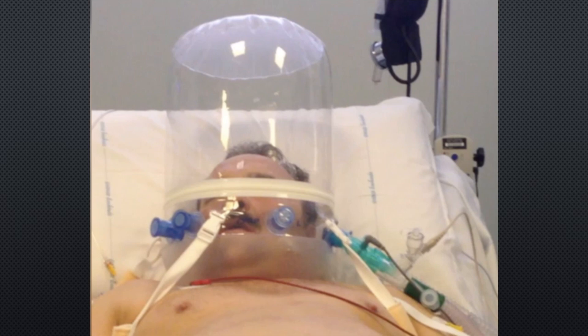The oxygen treatment hood available in Europe is designed to deliver non-invasive ventilation at a high rate of flow resulting in pressure that is slightly above normobaric pressures. It is important to realize that the oxygen hoods available in North America were originally intended for use in the hyperbaric environment and must be modified slightly to be used in the normobaric respiratory care role.